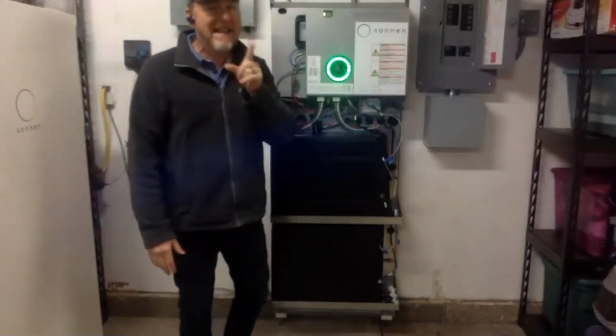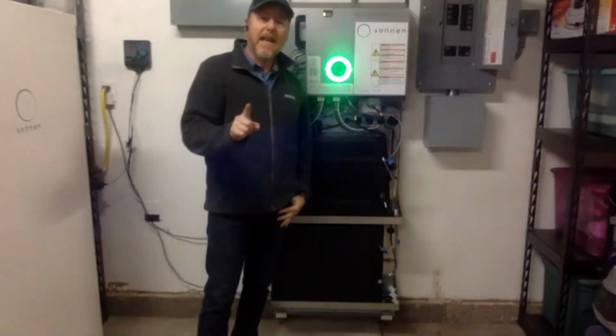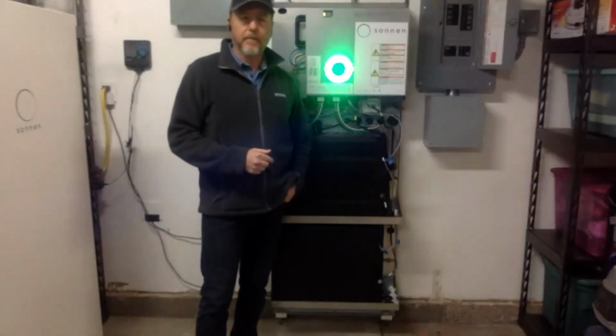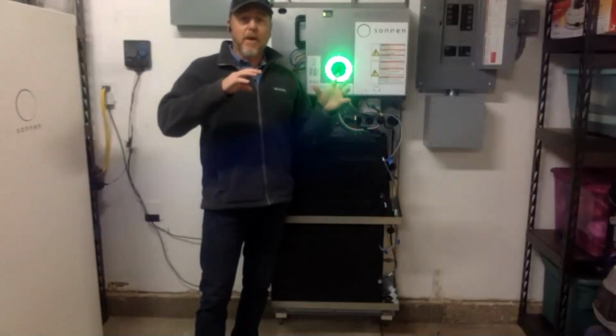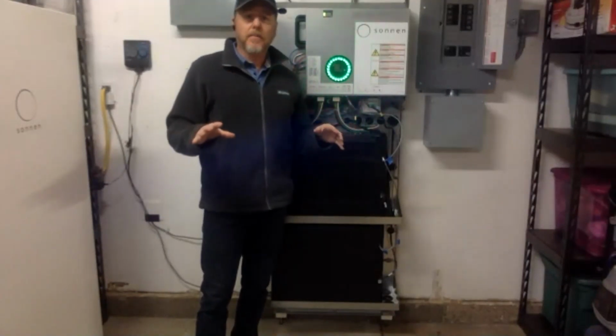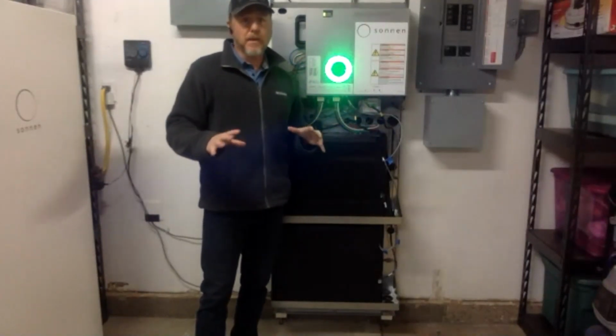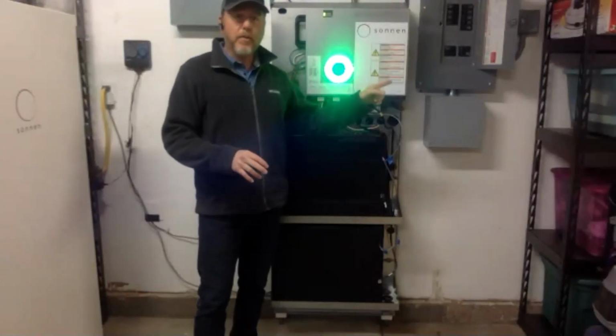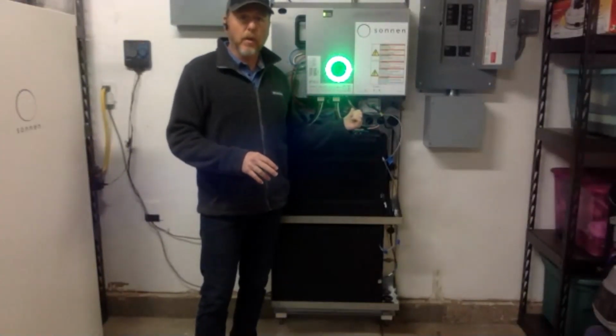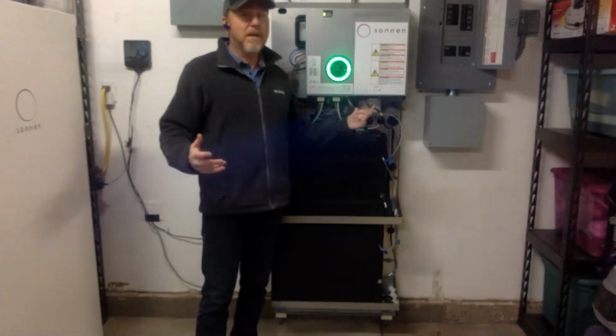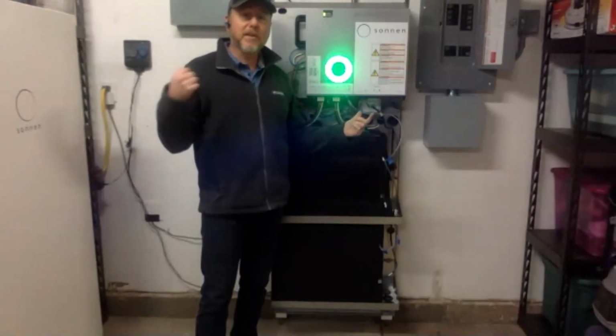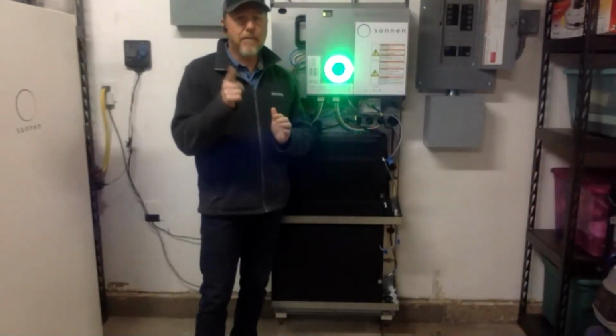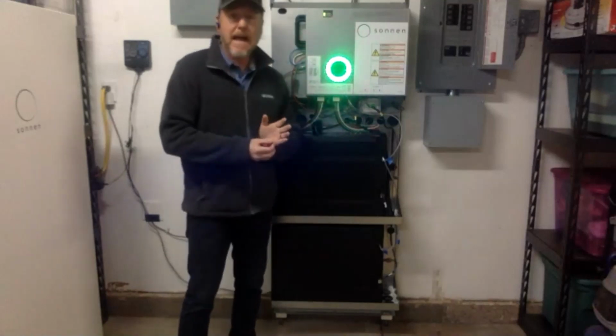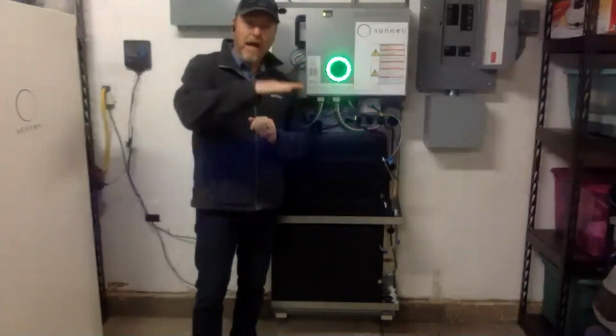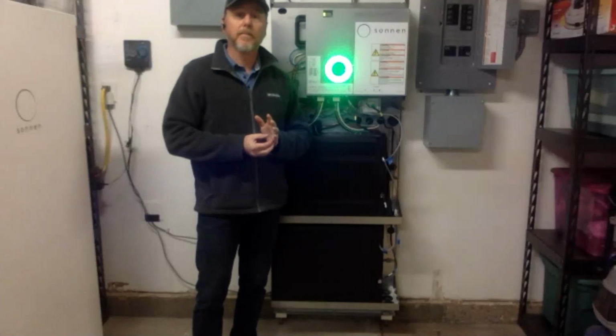But remember, AC coupled systems only get what is left over. So if I have 5,000 watts of load and only 2,000 watts of excess solar, then I'm not charging the battery. That's got to come from the grid if the grid is up, and it's not right now. So down goes your state of charge.